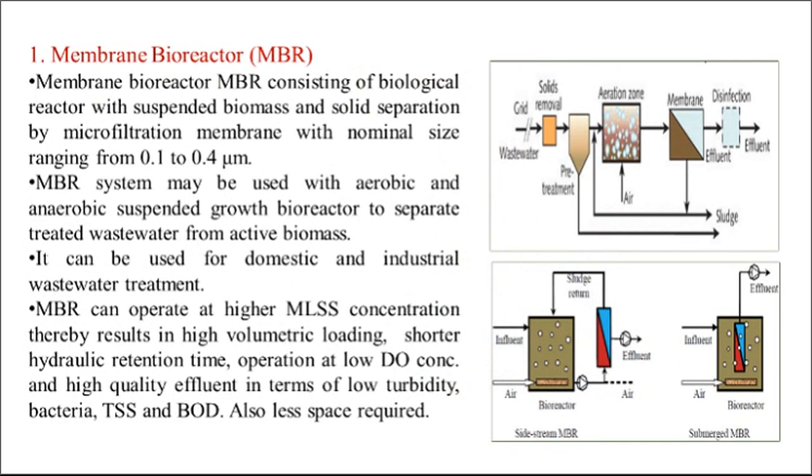Next one, membrane bioreactor, called MBR. A membrane bioreactor consists of a biological reactor with suspended biomass and solid separation by a microfiltration membrane with a nominal size ranging from 0.1 to 0.4 micron or micrometer. So whatever membrane we are using is of 0.1 to 0.4 micron size. So here we are using that particular membrane.